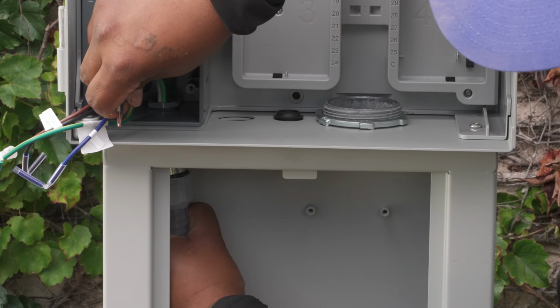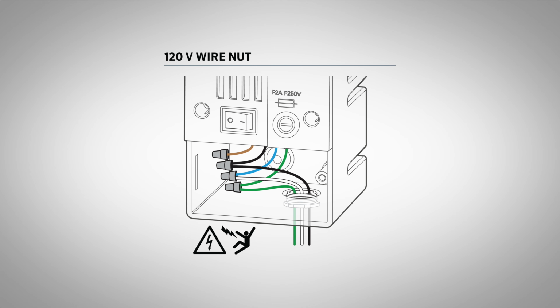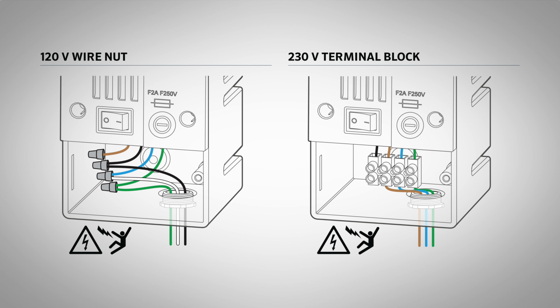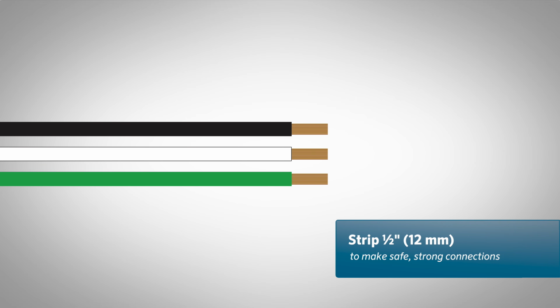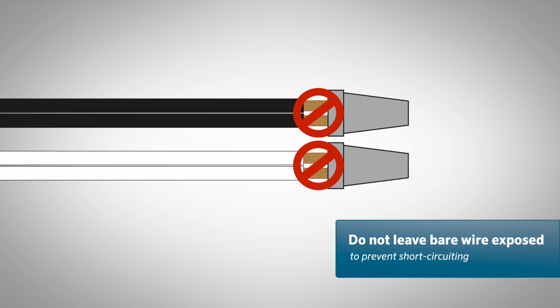Now we can complete the actual wiring connections. There are 2 different types of connections included with the controller. In North America, connections are commonly made with the wire nuts included. In some international markets, the Europa terminal blocks are required, also included. In either case, it's only necessary to strip about 1/2 inch or 12 mm of incoming power wire to make safe, strong connections. Do not leave additional bare wire extending out of the connector to prevent short-circuiting.